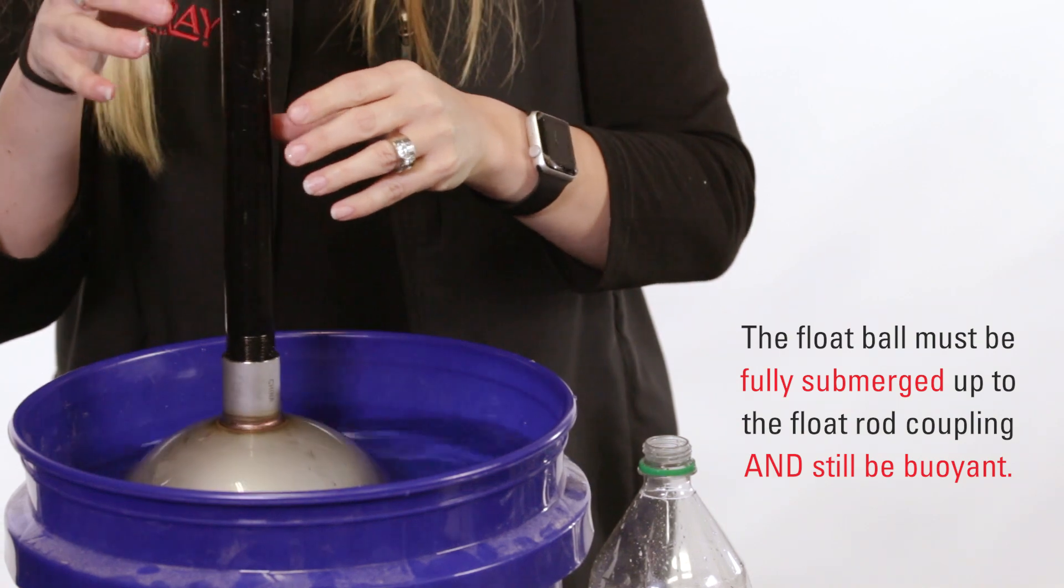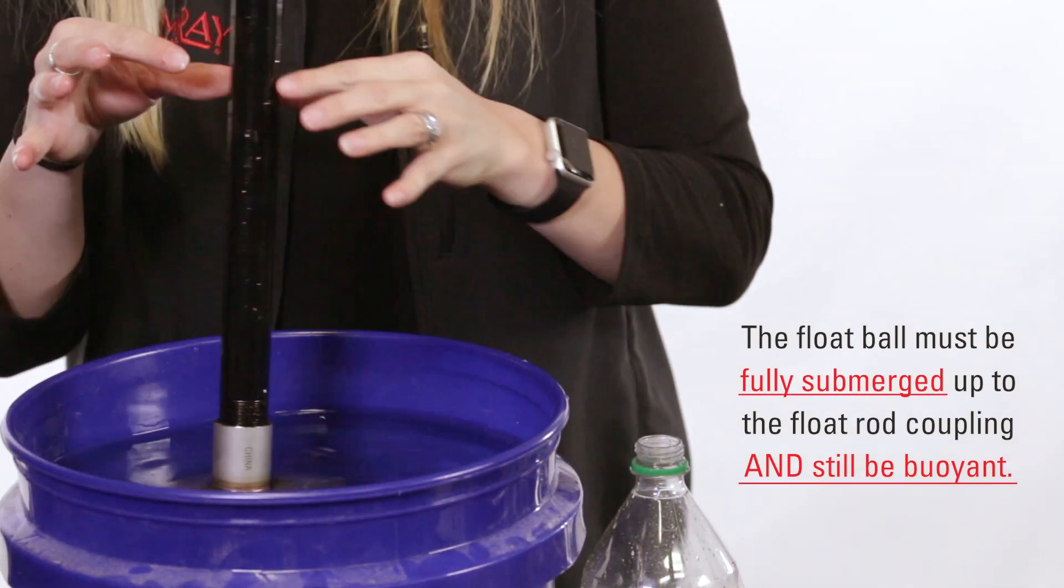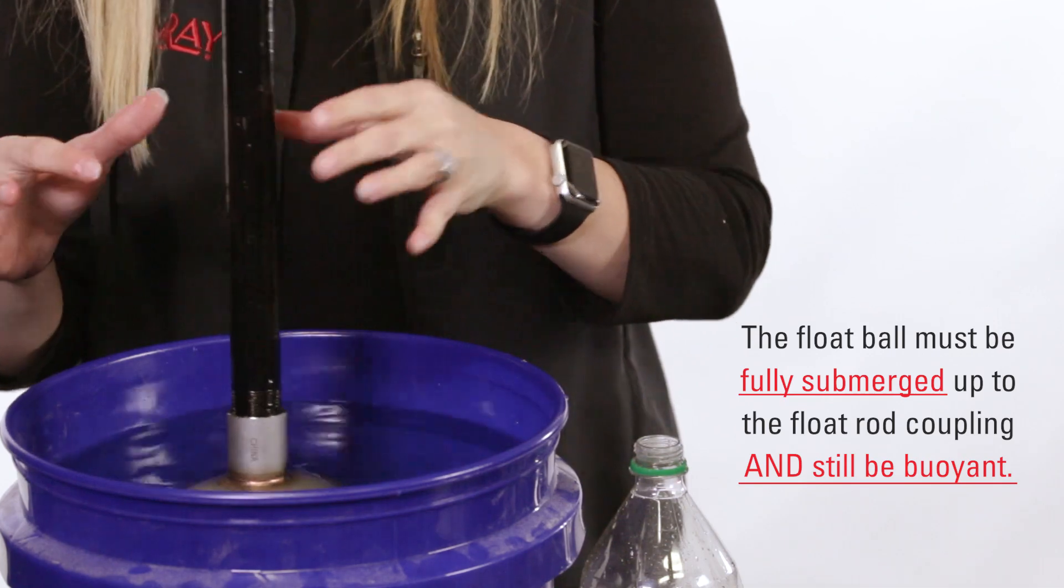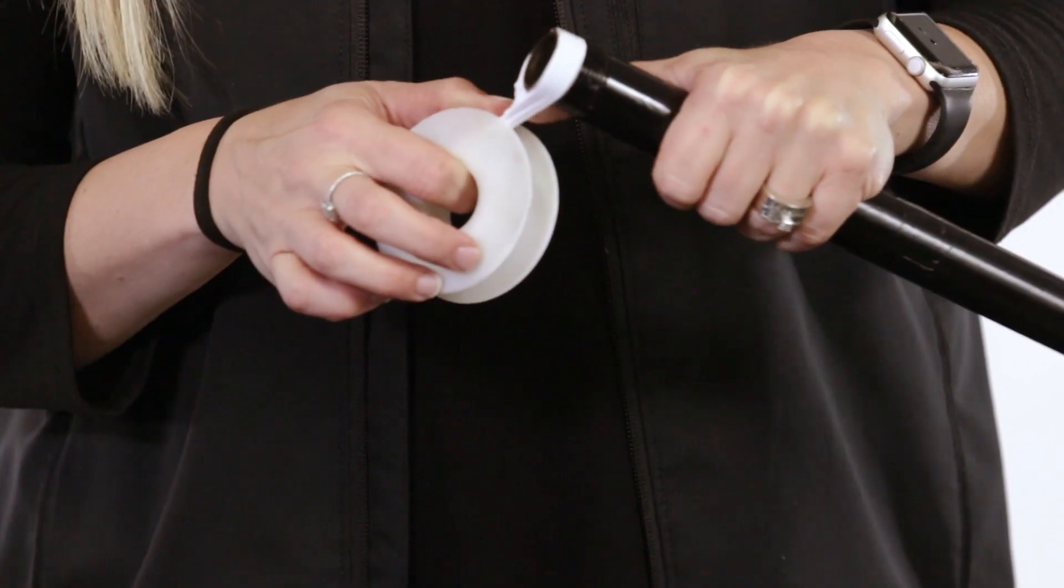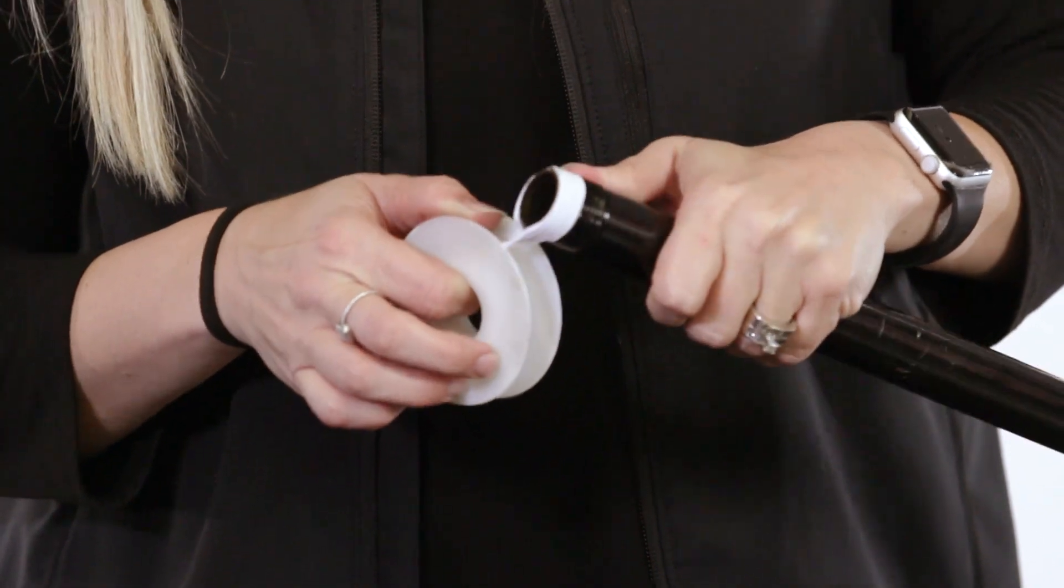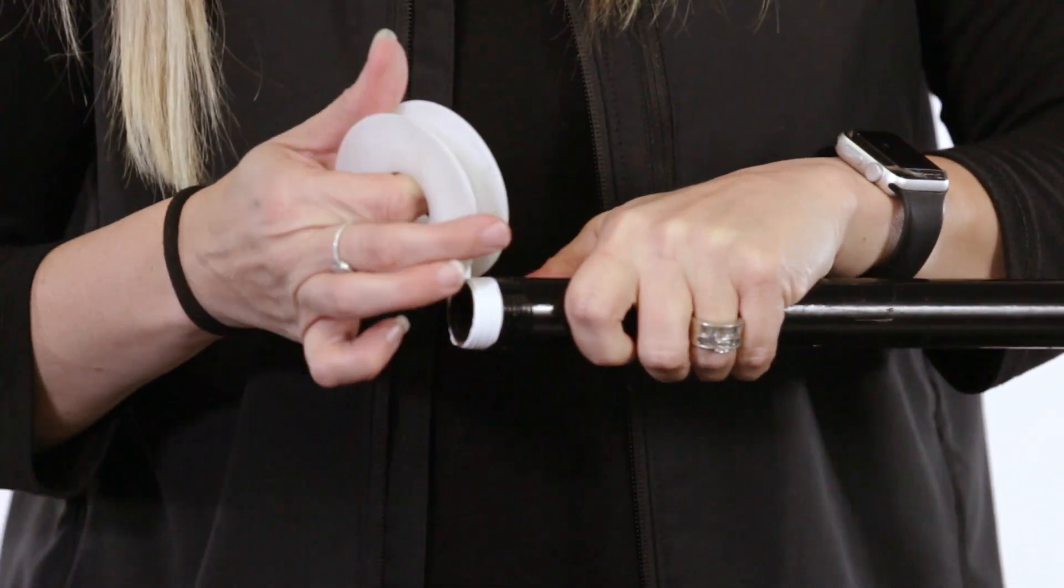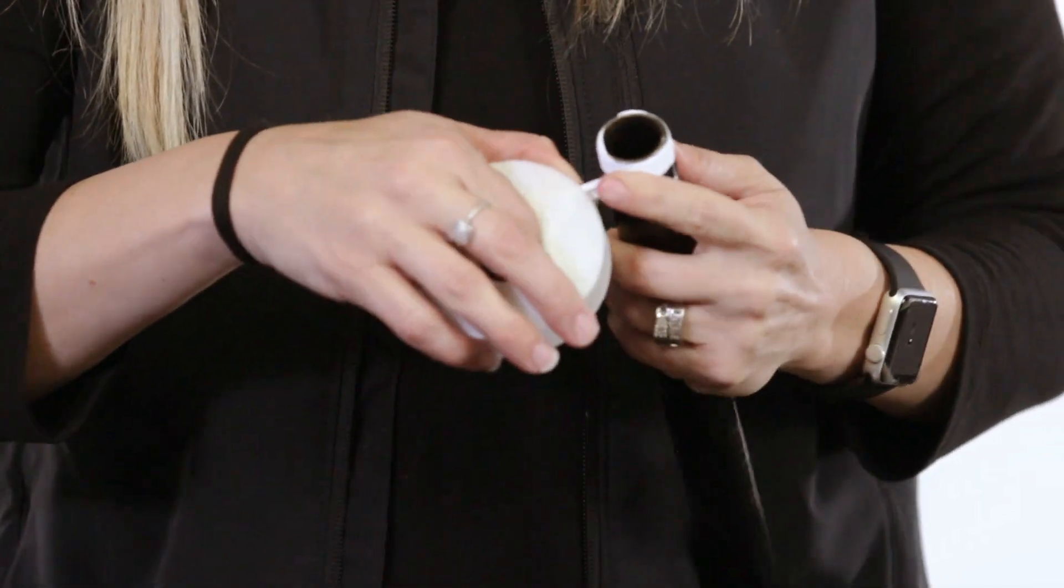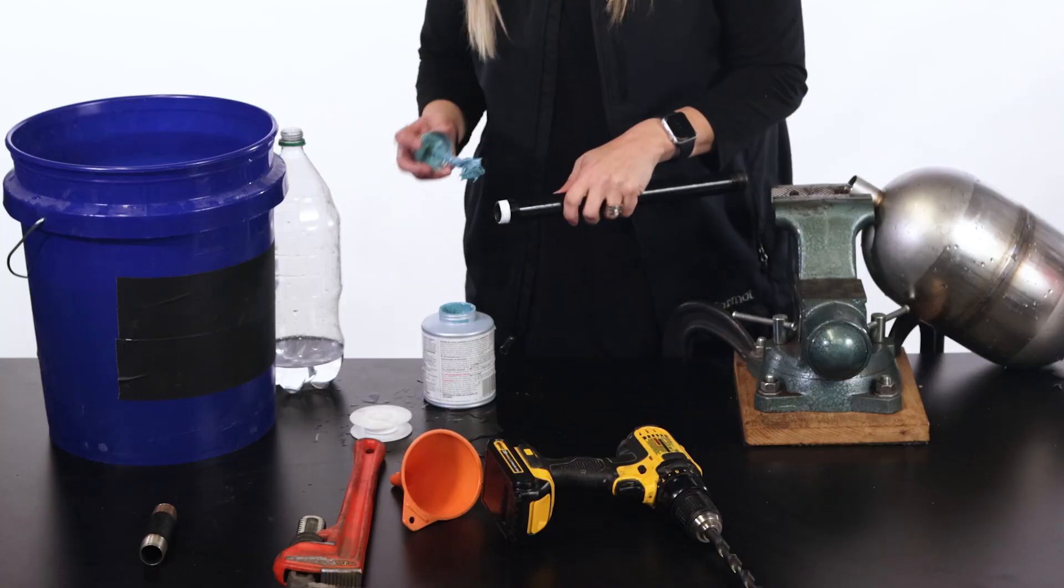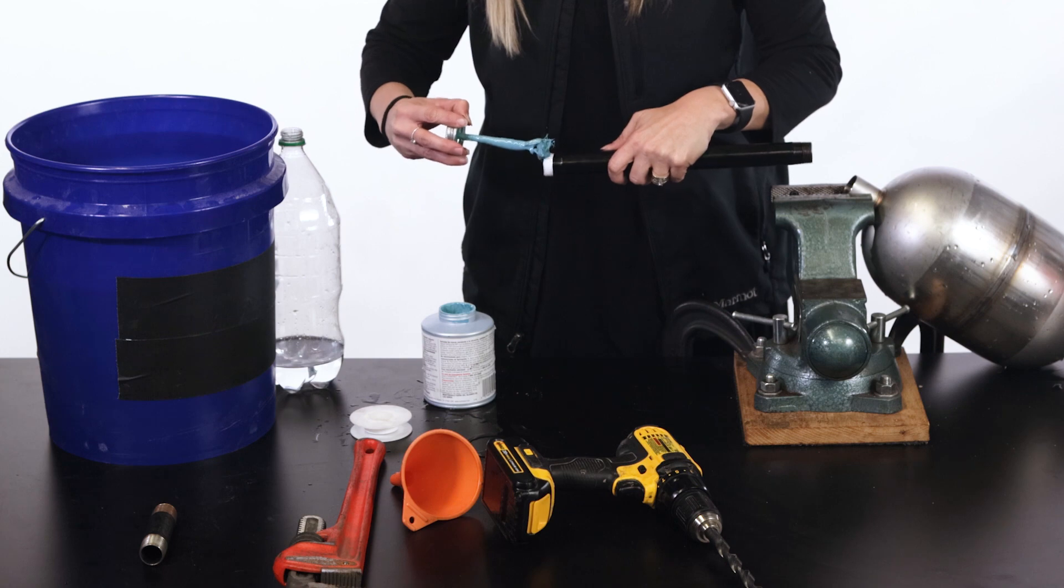If the float ball is fully submerged up to the float rod coupling and is still buoyant, you are now ready to seal the threads. Do this very carefully to achieve a good seal. We recommend also using pipe sealant. When the float is under pressure, water can easily be forced in.